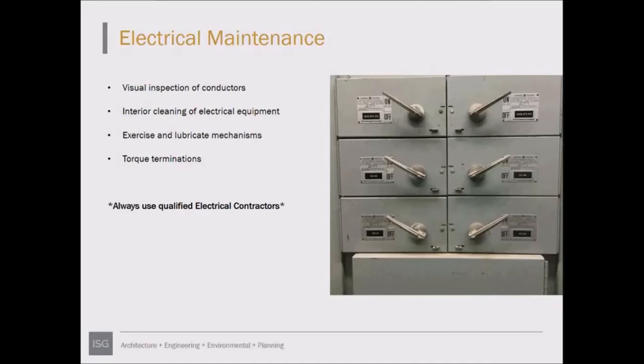Many of the older facilities have electrical gear similar to what's shown in the picture. There are movable parts inside, and often the equipment gets installed, turned on, and isn't touched for years. If these switches aren't exercised, they can become fused and not disconnect or reconnect. So when it comes to a construction project or service work, if you're not able to disconnect power because the gear hasn't been inspected or serviced, it could result in delays or replacement.